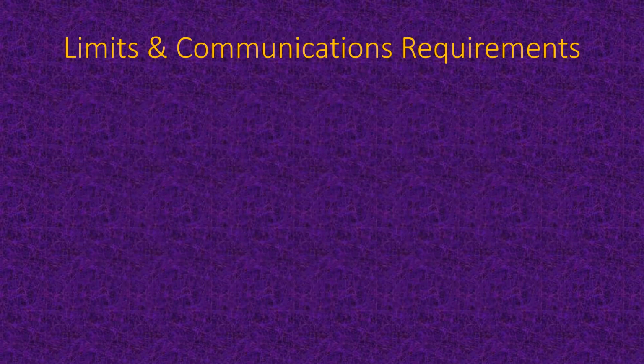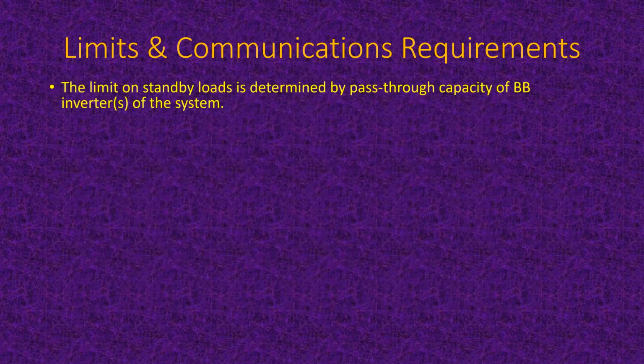Okay, limits and communication requirements. Standby loads are determined by the pass-through capacity of the battery backup inverters of the system. Because you can have a lot of standby load as long as you've got utility to feed them. But the National Electrical Code says that if there's no utility, then effectively your standby load system becomes a standalone system, and then the inverter does not have to be big enough to power everything. It simply has to be big enough to power the largest load of the standby loads. So those are things you think about when you're doing the design if you want to get it right.